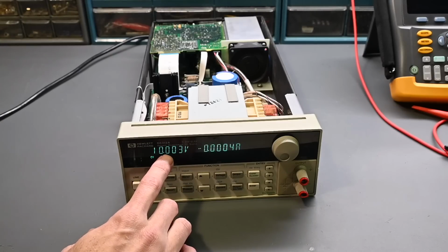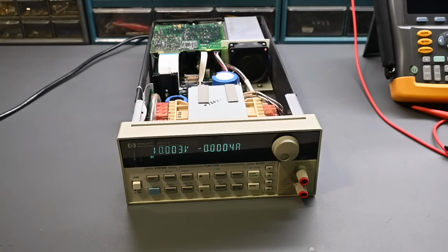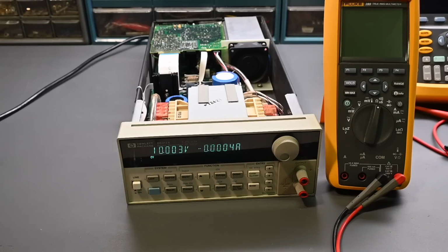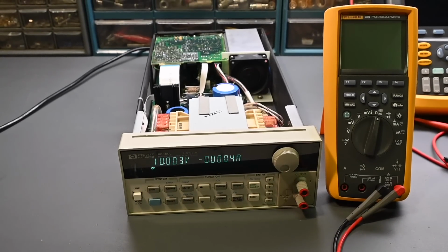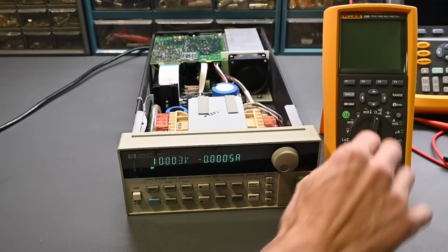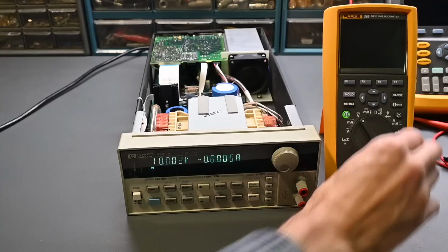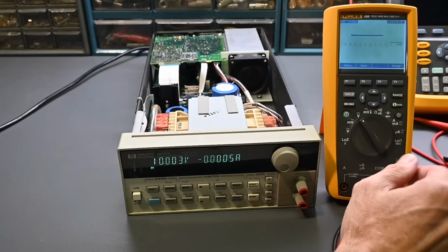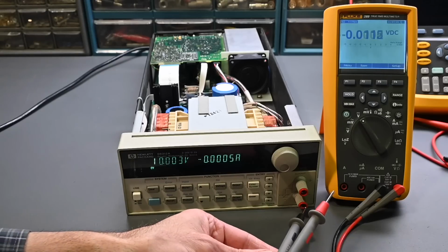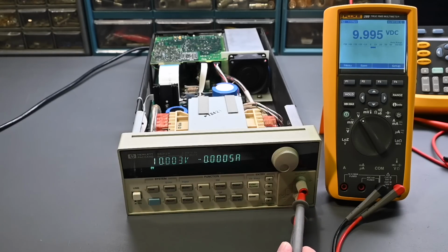This is a readback on the actual output that it's measuring, and it's sitting very close to the program value of 10 volts. So let's take a reading on the output terminals and see what the actual value is. I'll grab my digital multimeter. Let's see what we have here. You can see that in the display, in the camera. Okay, let's take a look. Hey, that doesn't look too bad. 9.995, very close to that 10 volt value. Again, I think with some calibration, it would bring these values right to where they should be. So that's looking very good.